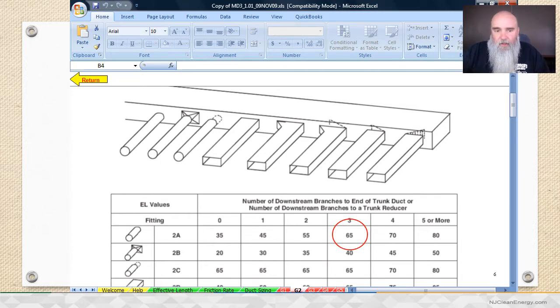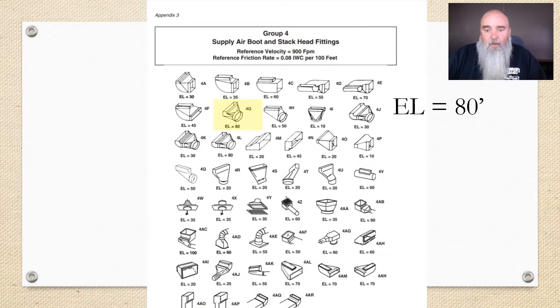Let's pretend that you already know this part, and what you know is these ELs. Where do they actually come from? Well, they come from a database from ASHRAE. Number one—number two, if you look at the top of this, the reference velocity is 900 feet per minute. So the equivalent length represents the pressure drop of the air moving around that fitting at 900 feet per minute.